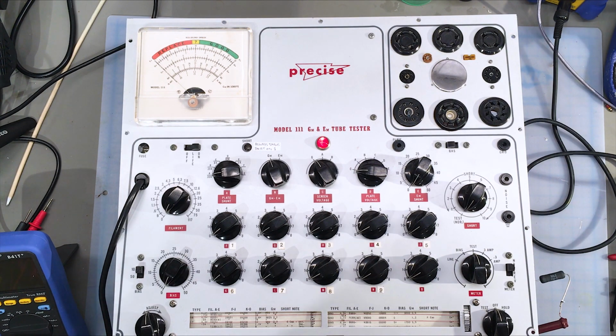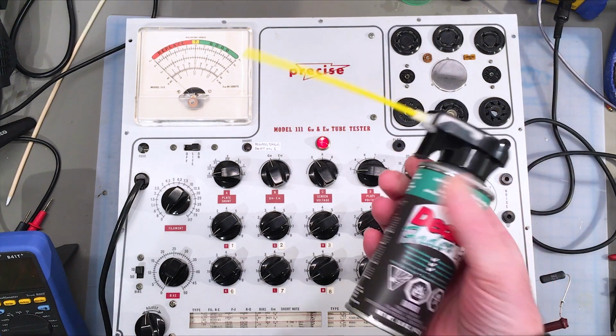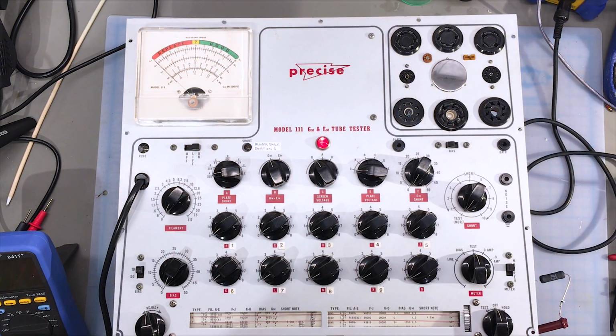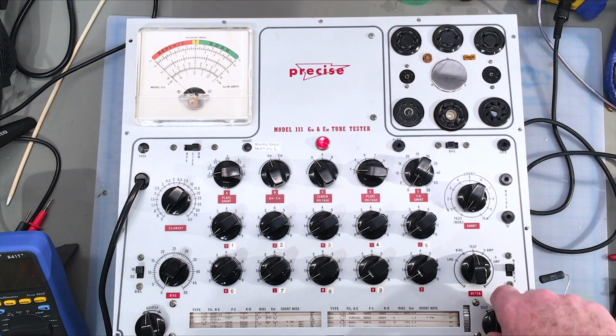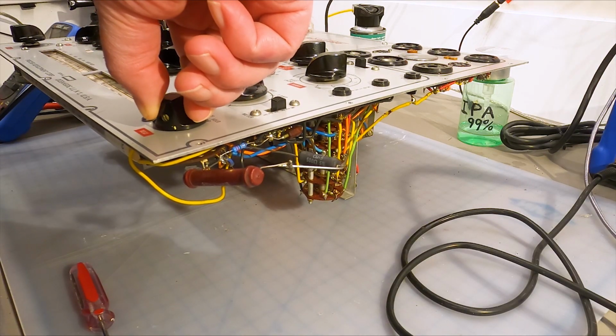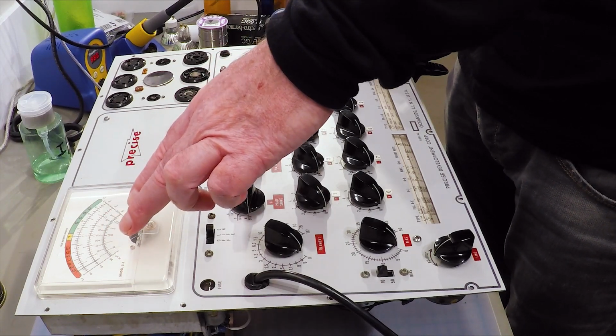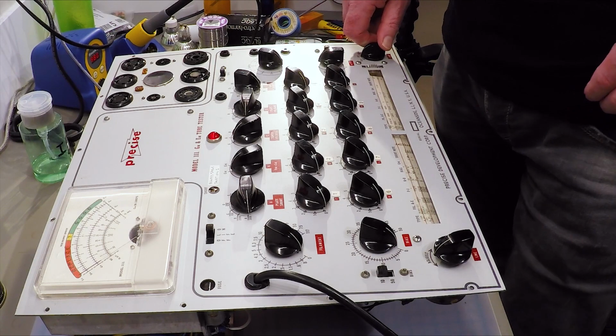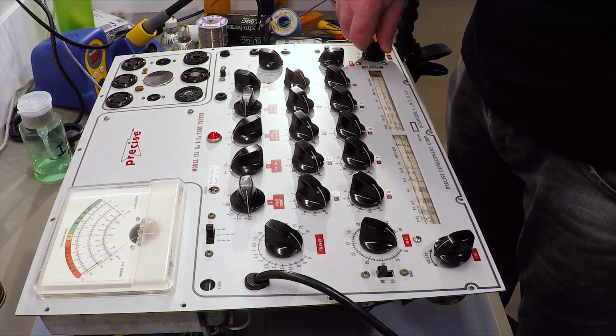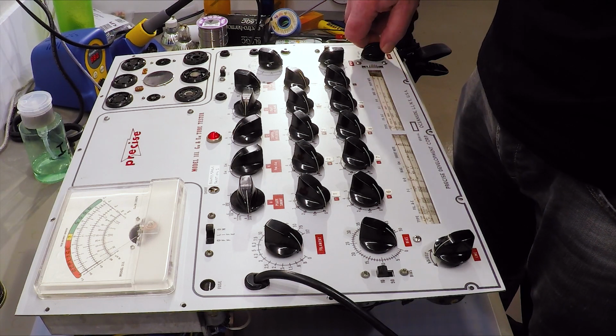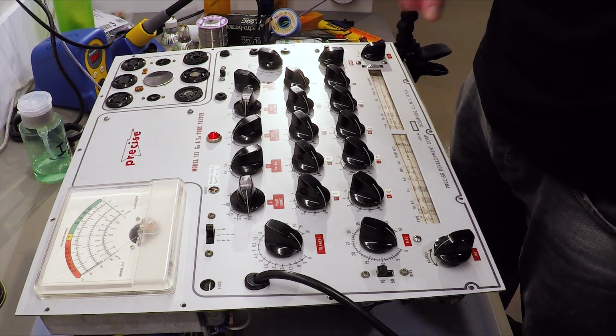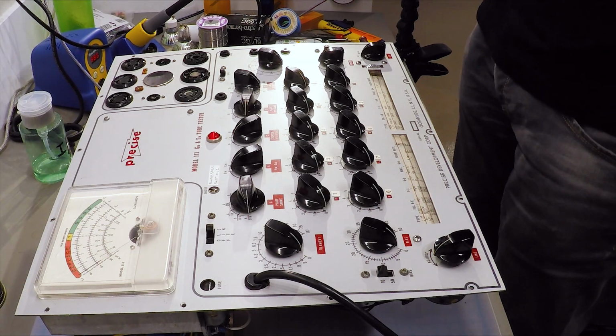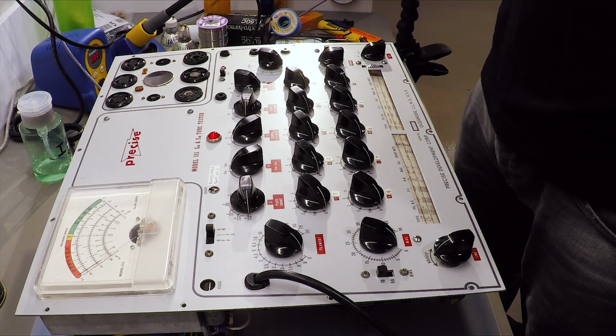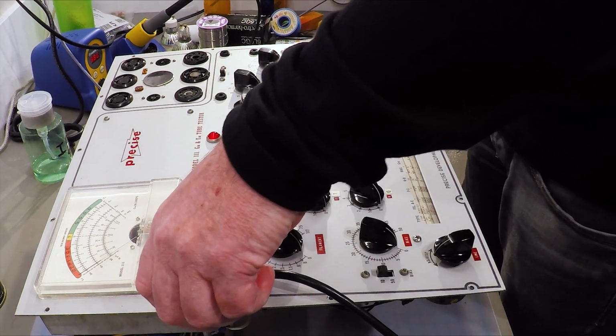So after some careful cleaning of the potentiometer P4 with DeoxIT FaderLube F5, I have managed to get the potentiometer adjusted to a point whereby when I switch the test switch from off to test, although there is initially a minor deflection on the meter, which could be positive or negative depending on where in the cycle I move the test switch, it settles back at the 0 deflection point. And that's exactly where we want it. And so I consider this to have been adjusted. And now we can move on to the GM adjustment portion of the calibration.